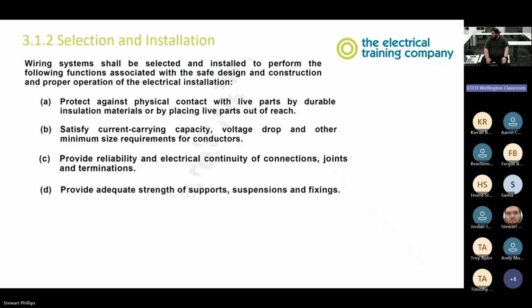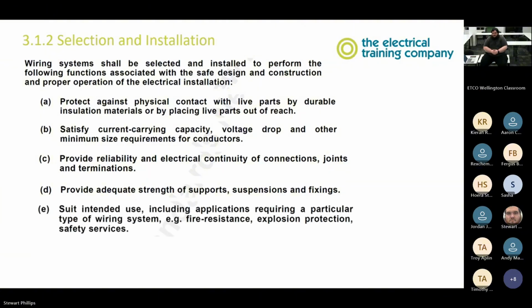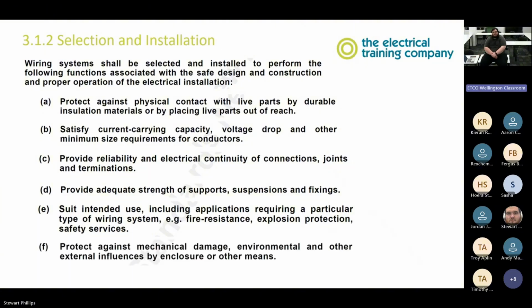So provide adequate strength and supports, suspensions, and fixings. So we need to make sure that our supports are strong and that they're not flimsy, and they're very good suspension systems. They need to be suitable for the intended use, including requiring a particular type of wiring system, so fire resistant and explosive protection. So depending on whether we use PVC or steel, might be dependent on whether we have to survive an explosion or other things. So protect against mechanical damage. So if we know there's going to be a high likelihood of mechanical damage or mechanical impact, we need to use a stronger wiring enclosure for this.